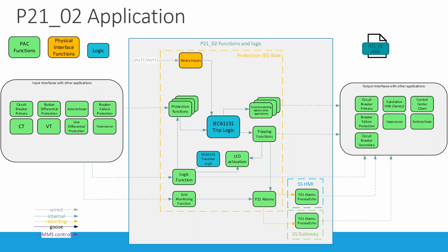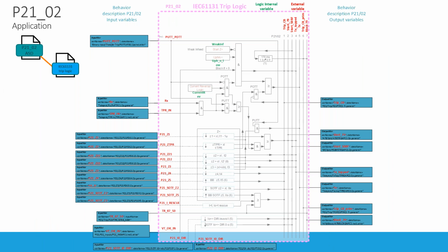Coming back to the big blue box in the middle, the 61131 trip logic: this logic comes from the concept we have within Elia, and it allows us to document in the 61131 language how all the signals need to be treated and how the trips and other signals are created from it. This is really added value enabled by the behavior descriptions that can now be attached to the applications.